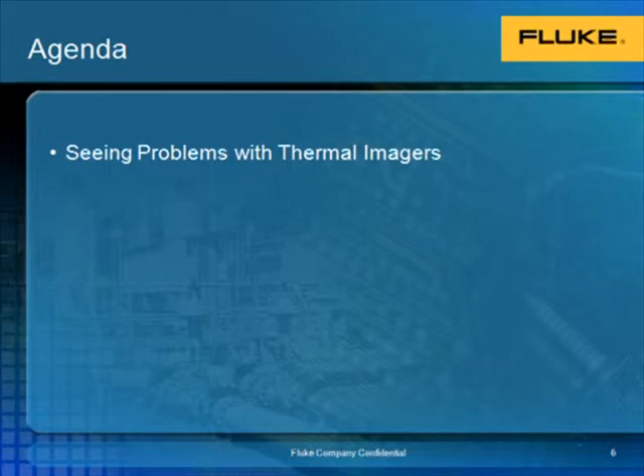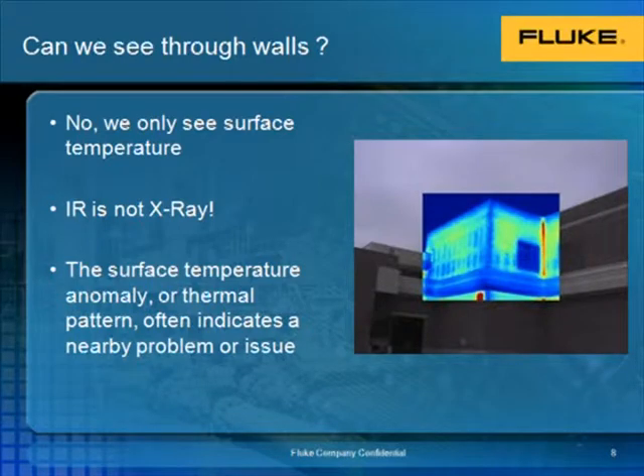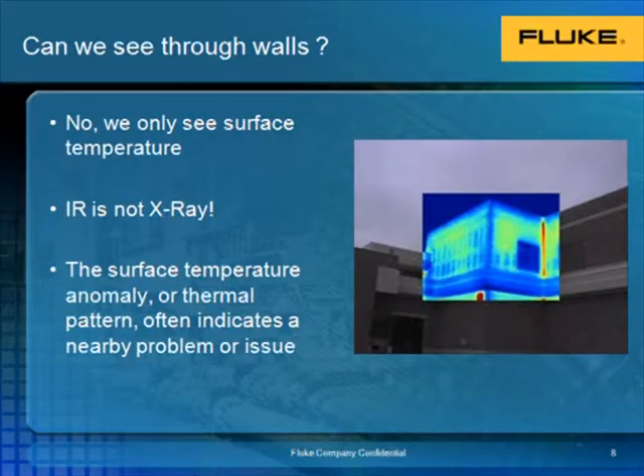As we go through the next few slides, we'll learn how thermal imagers are able to see these various problems. It is important to note that thermal imagers do not see through walls — they detect surface temperature only. Infrared is not the same as x-ray. By singling out surface temperature anomalies, or by examining the thermal pattern, we can often pinpoint where a nearby problem or issue may be.